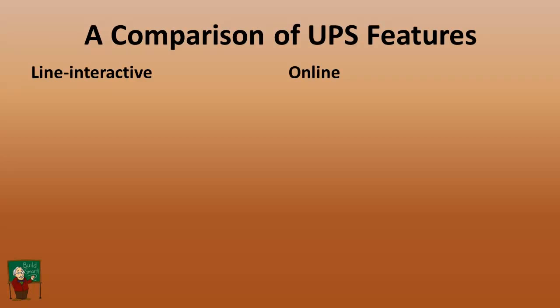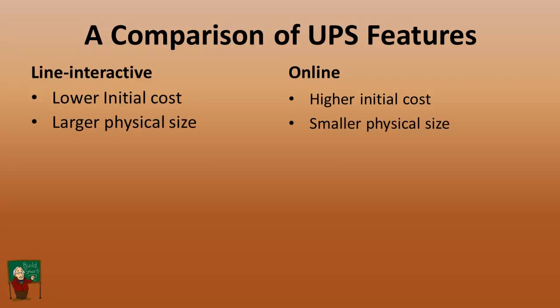The line interactive is a very little more expensive than the standby type. So most of the ones, particularly in commercial use, are the line interactive at the lower end. The line interactive has a lower initial cost than the online. It's because it doesn't have as large components in it in terms of the rectifier, and it's not working the same amount of time. The line interactive is typically larger physical size. Online would usually be somewhat smaller.